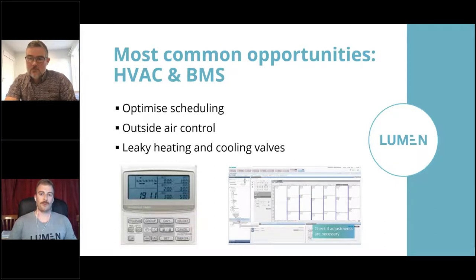So for larger buildings, when you've got a more complex HVAC system and a building management system, the two most common issues we come across that waste a lot of energy are outside air control and leaky heating and cooling valves. You need to bring in some outside air into a building to provide adequate ventilation for the people in there. However, most buildings are bringing in excessive amounts of outside air, and it's really expensive to heat and cool. The most common issues that we see that cause this are faulty CO2 sensors, which can be used to determine how much ventilation you need, and broken outside air dampers. I recently heard someone say that there's two types of outside air dampers, broken and about to break, and that's right on the money from what we've seen.